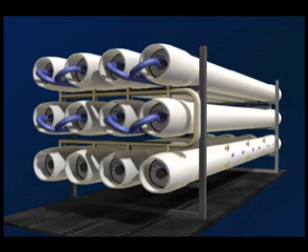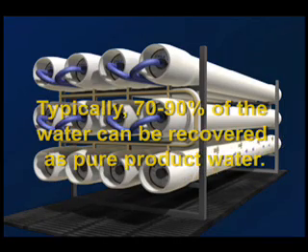The permeate water then flows out the end of the vessel and is collected as the product. And the reject or concentrate from that vessel may then flow through another vessel producing more permeate. The remaining concentrate may then be disposed of as waste or partially recycled as the feed. Typically 70-90% of the water can be recovered as pure product water.